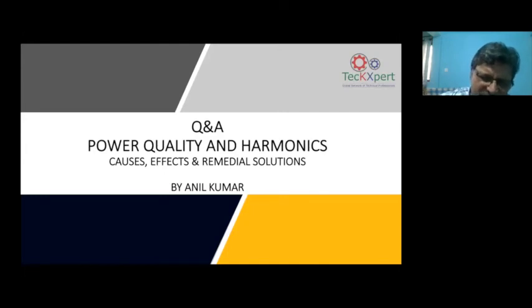Where do even harmonics come from? Normally, if you have a perfect rectification of a sine wave, as I said in the beginning of the slides, in a UPS or a VFD or an LED or a CFL, the rectification is full wave, with a perfect matching of the positive and negative sides of the waveform, symmetrical waveforms. Even harmonics come when the symmetry is gone. If the firing angle in VFDs or electronics is not synchronized or not working according to the design, it certainly produces even harmonics, because the rectification is then not symmetric. Sometimes it can also contain non-integer harmonics. That means instead of the second harmonic, you can have a 2.5 harmonic also.